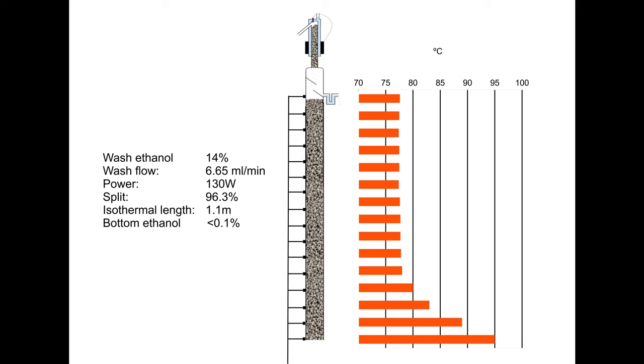If the isothermal section gets too short, we reduce the steam flow. If the bottom temperature gets too low, we increase it. The length of the isothermal section is pretty easy to measure — the temperature rises quite quickly below it, so you don't have to be that precise in temperature measurements.